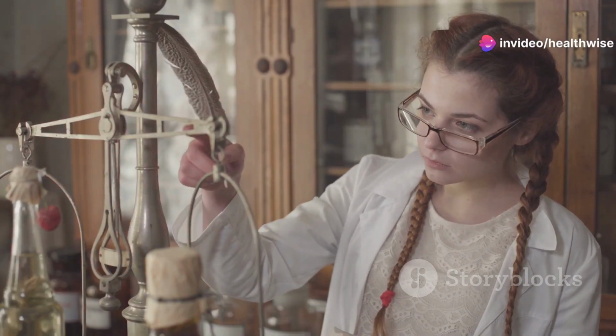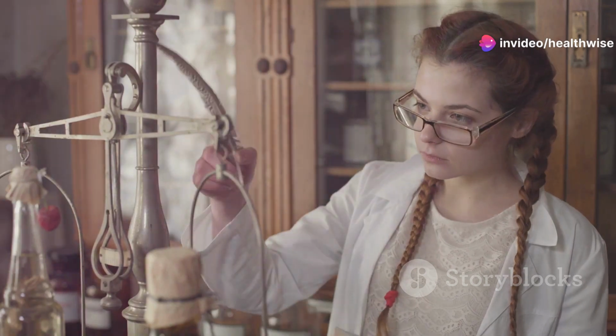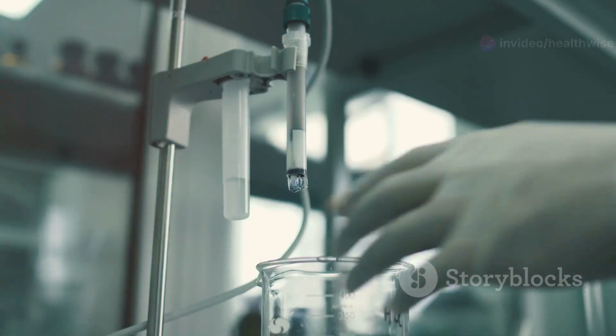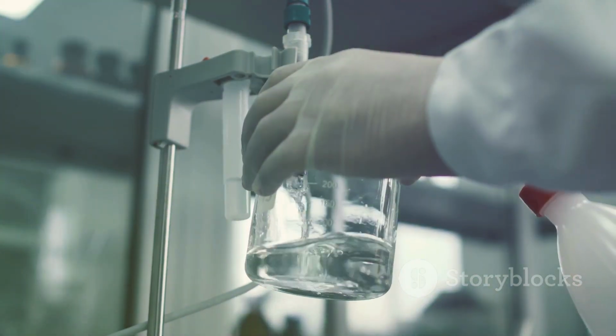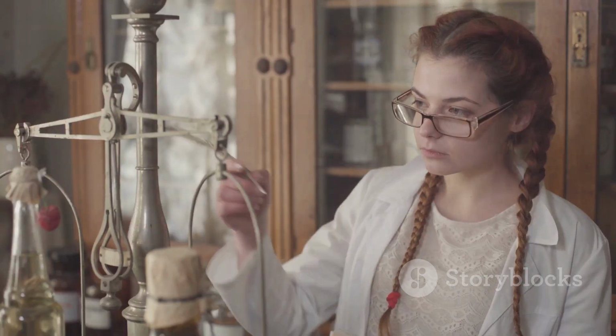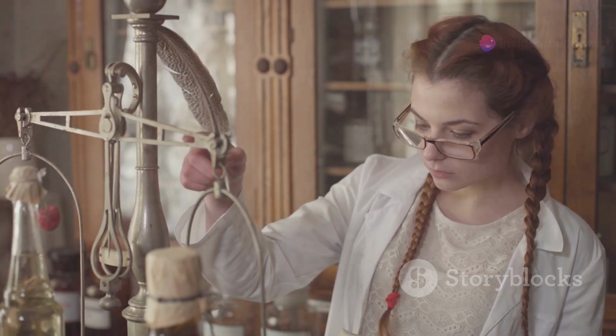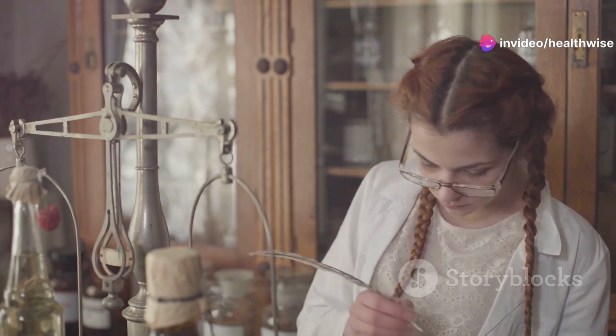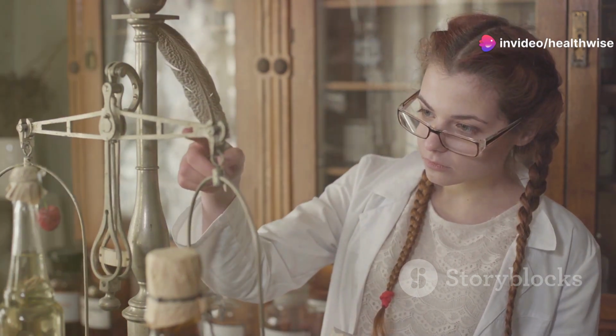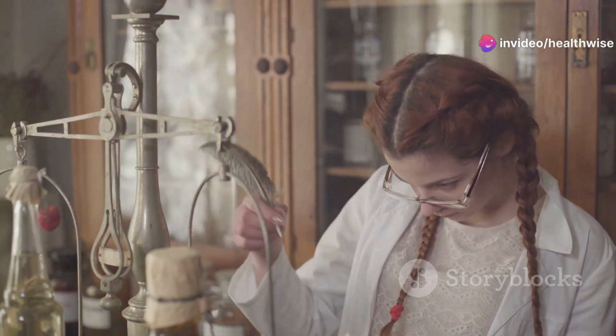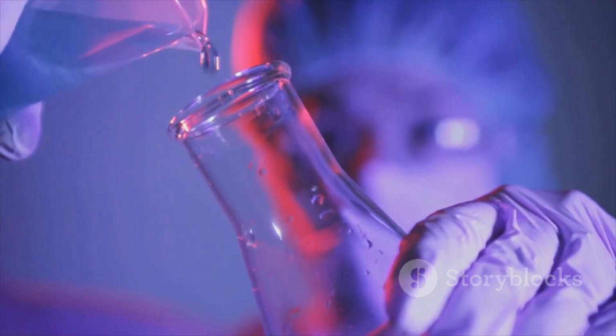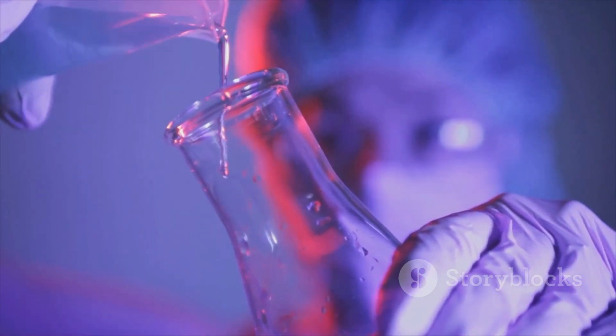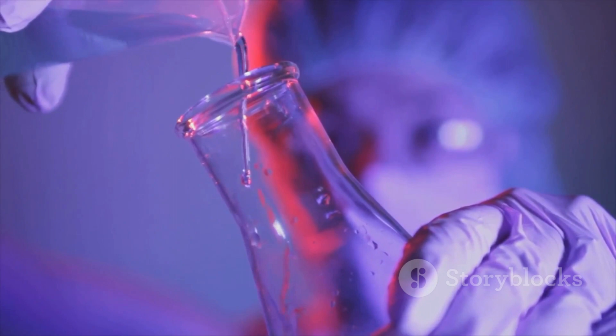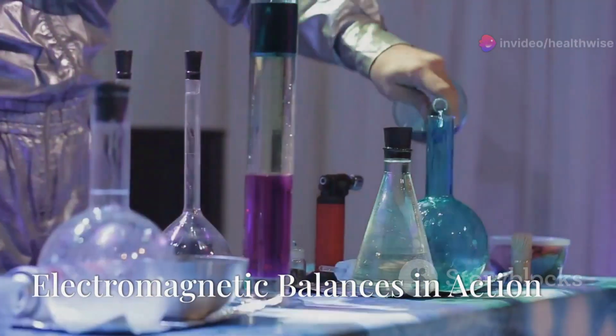Secondly, avoid overloading the balance. Each balance has a maximum capacity. Exceeding this limit can damage the instrument or affect its accuracy. Always check the manufacturer's specifications and stay within the designated weight range. Thirdly, remember that even the smallest air currents can influence measurements. Avoid drafts, sudden movements, or even breathing directly on the weighing pan, especially when dealing with minute masses.